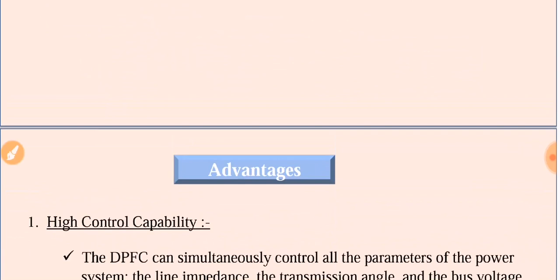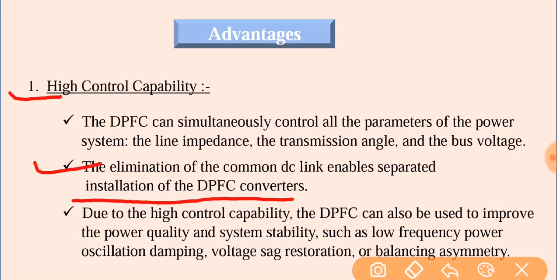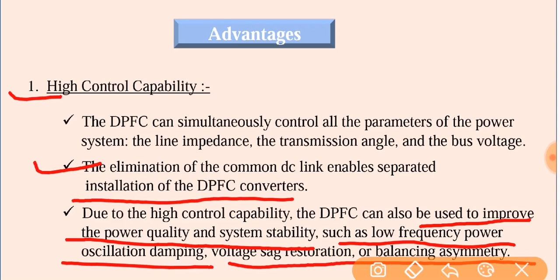Now we discuss the advantages of the DPFC. The first advantage is high control capability. This means the DPFC can simultaneously control all the parameters of the power system: the line impedance, the transmission angle, and the bus voltage. The elimination of the common dc link enables separate installation of the DPFC converters. Due to this high control capability, the DPFC can also be used to improve power quality and system stability, such as low frequency power oscillation damping, voltage sag restoration, or balancing asymmetry.